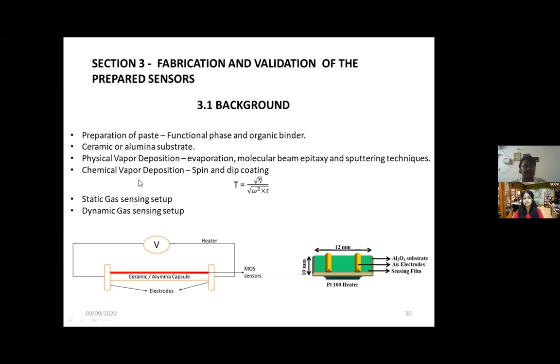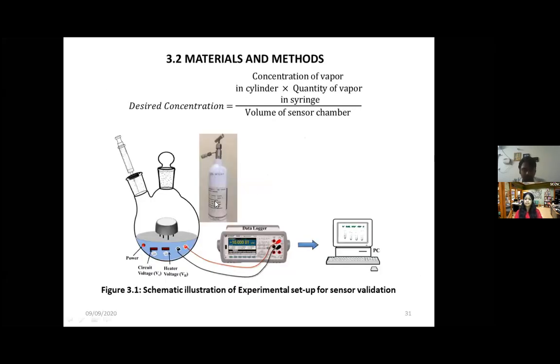And for validation, we have two setups, static and dynamic gas sensing setup. The dynamic gas sensing setup replicates the real world environment. But the problem we face is that in the dynamic gas sensing setup, if there is an error, we have to go back to the first step, and there is not much manual control. However, the static gas sensing setup is manually controlled. We have a pre-calibrated cylinder. Place the gas-tight syringe on the mouthpiece of this pre-calibrated cylinder, turn this. So based on the pressure, the needle goes back and the gas is injected into the static gas sensing chamber.